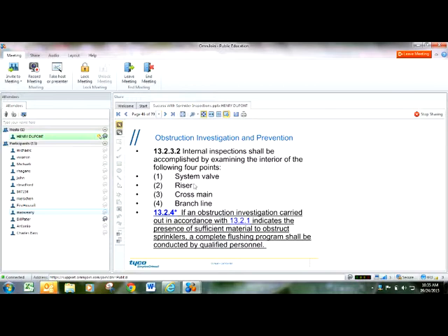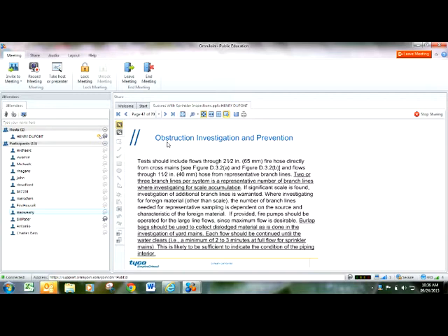These are the points of the system where we do our inspections for the 5-year obstruction investigation. If an obstruction investigation carried out in accordance with this section finds significant material to obstruct a sprinkler, a complete flushing program shall be carried out. So if we find during our 5-year obstruction investigation that a system is questionable about having obstructing debris in it, NFPA 25 tells us that we can flush a representative sample of sprinkler branch lines, which is 3 generally, and a representative sample of mains, which is 1.